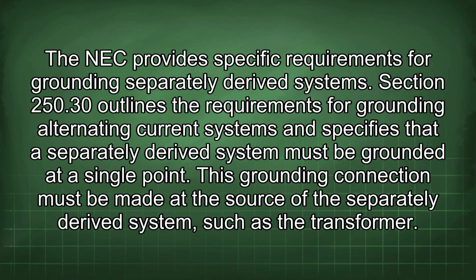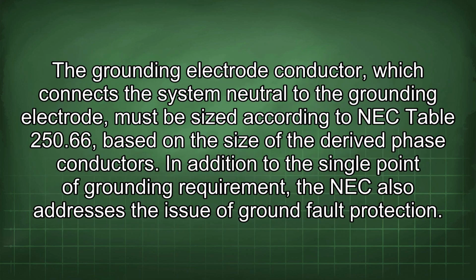The NEC provides specific requirements for grounding separately derived systems. Section 250.30 outlines the requirements for grounding alternating current systems and specifies that a separately derived system must be grounded at a single point. This grounding connection must be made at the source of the separately derived system, such as the transformer. The grounding electrode conductor, which connects the system neutral to the grounding electrode, must be sized according to NEC Table 250.66, based on the size of the derived phase conductors.